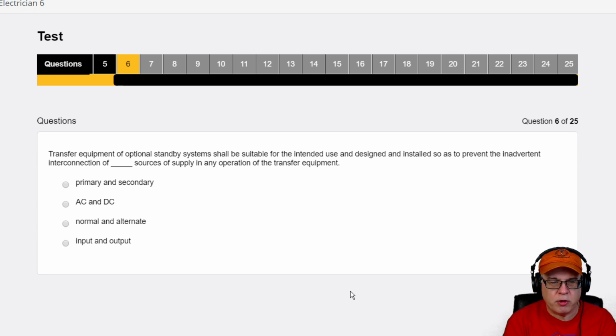Transfer equipment of optional standby systems shall be suitable for the intended use and designed and installed so as to prevent the inadvertent interconnection of sources of supply in any operation of the transfer equipment. Obviously we have to have the ability so that it can't connect to the utility as well as to the generator at the same time. That would be pretty bad, right? So there's an interconnection there, okay.